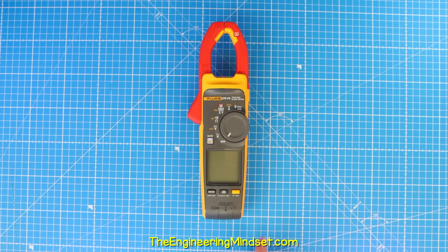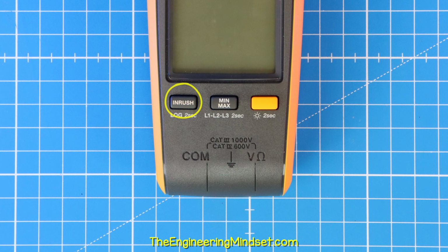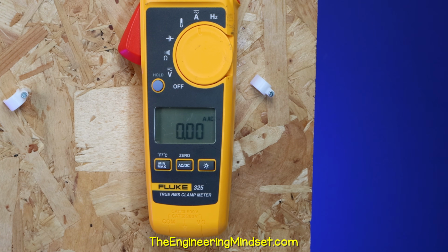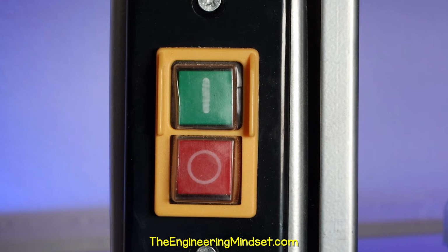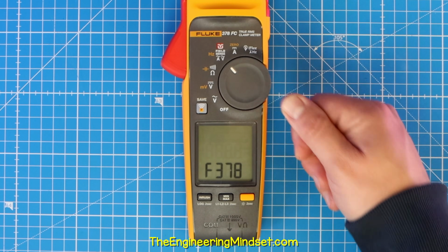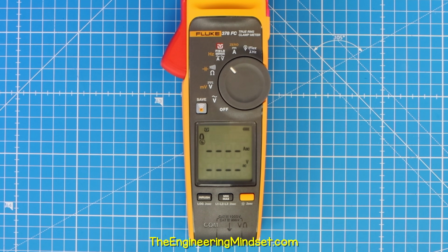If your meter shows the inrush current function, then you can measure this. But standard clamp meters can only measure running current. Ensure that the device is turned off. For auto range, select the AC current function for the clamp jaw and press the Inrush button.